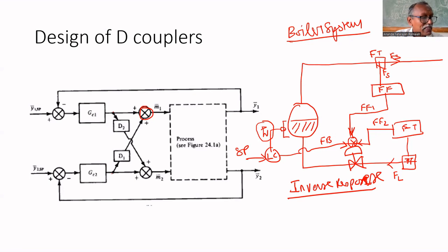If the inlet flow rate increases, what will happen? The temperature will decrease. That's why the boiling of this water will be quenched. As the boiling of the water is quenched, the apparent level decreases. We know that while the water is boiling, the apparent level will be higher. The transmitter gives apparent level only, but the apparent level goes down. So if you increase the inflow rate, level has to rise. Instead, initially it appears that level decreases. That is called inverse response.